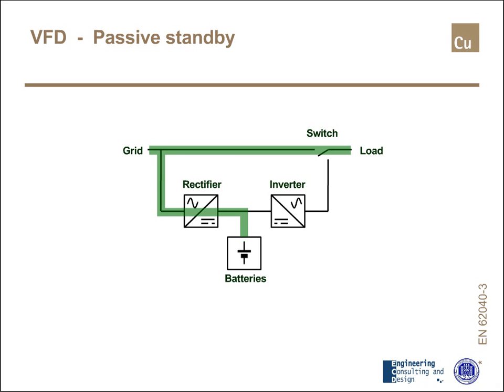With the network, energy flows to the load through the green line, and at the same time recharges the batteries. Typically, voltage and frequency dependent UPS are also called passive standby, and looking at the market there is practically full correspondence between these two classes. But theoretically, VFD does not necessarily mean passive standby.